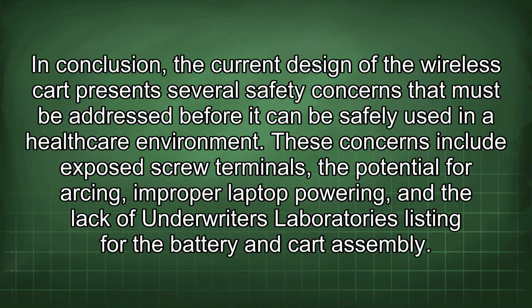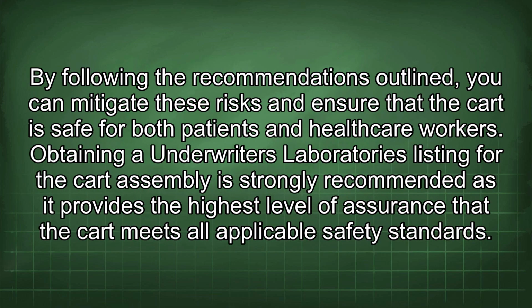In conclusion, the current design of the wireless cart presents several safety concerns that must be addressed before it can be safely used in a healthcare environment. These concerns include exposed screw terminals, the potential for arcing, improper laptop powering, and the lack of UL listing for the battery and cart assembly. By following the recommendations outlined, you can mitigate these risks and ensure the cart is safe for both patients and healthcare workers. Obtaining a UL listing for the cart assembly is strongly recommended as it provides the highest level of assurance that the cart meets all applicable safety standards.